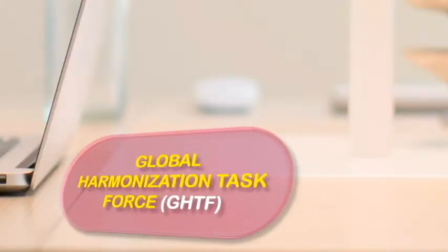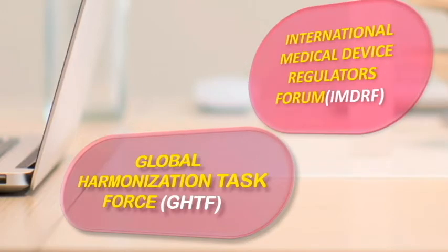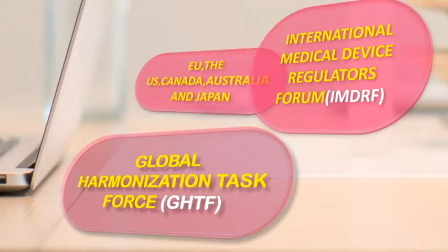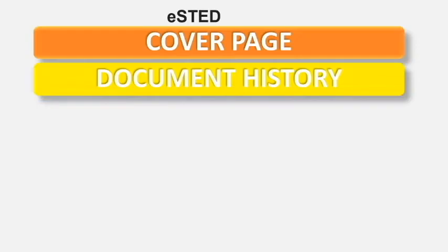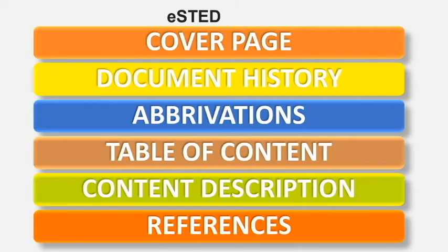The STED template is prepared by the Global Harmonization Task Force, and it is input for the International Medical Device Regulators Forum for the medical device regulatory submission. Not only the EU, the US, Canada, Australia and Japan are using the STED for submission. The electronic form of STED is called eSTED. eSTED consists of cover page, document history, abbreviations, table of content, content description and references.